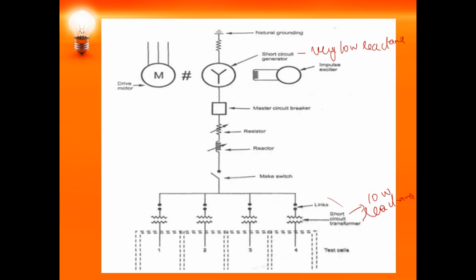Next, how should this work? When a short circuit current is flowing, the circuit breaker under test has to trip. If this doesn't trip, what will happen? This entire setup will get damaged. So in order to protect this entire setup, you have a master circuit breaker. The master circuit breaker is a backup circuit breaker. If the circuit breaker under test fails to operate, then your master circuit breaker has to operate. After every test, you have to check the circuit breaker under test.